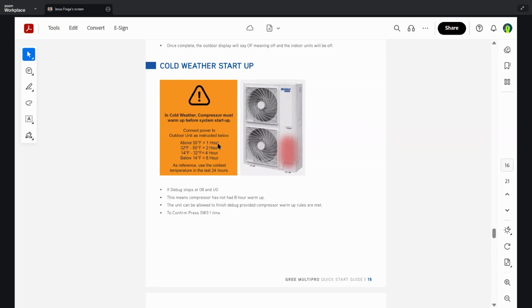So we know that anything above 50 degrees is going to be a 1-hour warm-up period. Anything between 32 and 50 is going to be a 2-hour. Anything between 14 and 32 is going to be a 4-hour. And anything below 14 is going to recommend that 8-hour warm-up period.